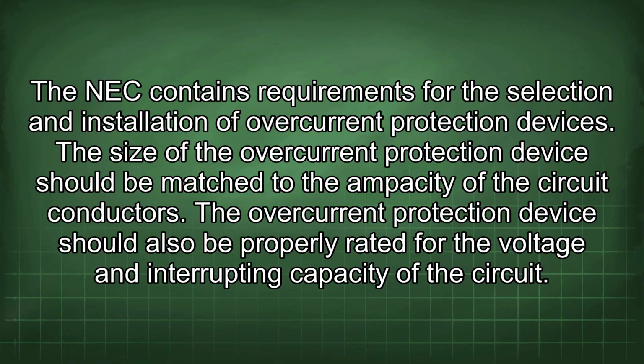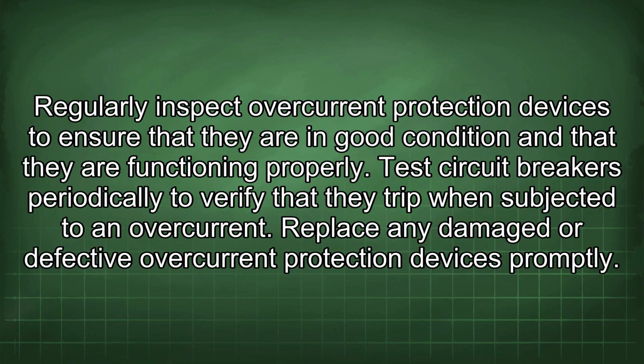The size of the overcurrent protection device should be matched to the ampacity of the circuit conductors. The overcurrent protection device should also be properly rated for the voltage and interrupting capacity of the circuit. Regularly inspect overcurrent protection devices to ensure that they are in good condition and that they are functioning properly. Test circuit breakers periodically to verify that they trip when subjected to an overcurrent. Replace any damaged or defective overcurrent protection devices promptly.